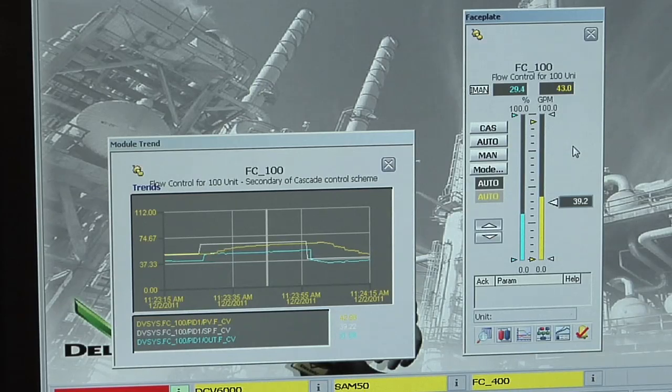But I might also note that at the top of the control window at the PID controller, we'll see a digital value, and that digital value is actually set up to show the true stem position, not the implied stem position. So the operator can look on this screen right away and know that my valve has moved to a particular position, which means there's no need to necessarily send somebody out to the field to go look at the position. So they have much faster feedback on what's going on with their process equipment. In this case, 30 point some percent.